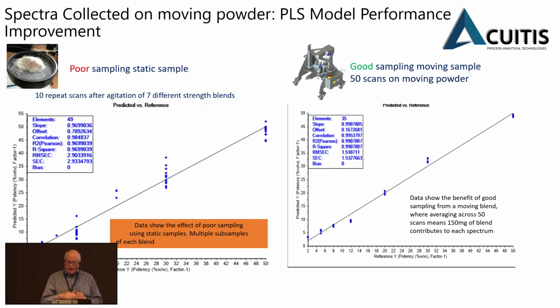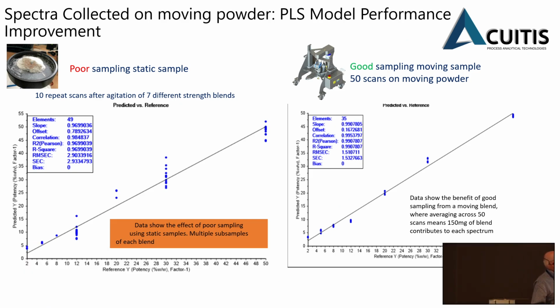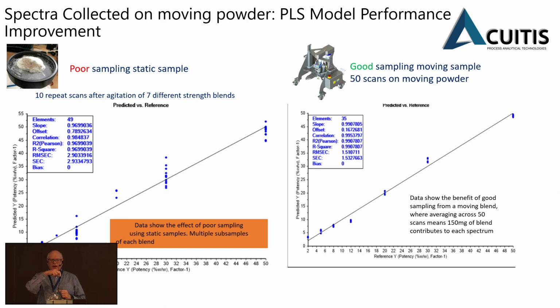Now, the way we get around that, I'll come to in a minute, but here is some evidence that this is a real big problem. Myself and Owen actually did this work. We scanned a blended powder on a dish where we were just covering the fiber optic probe. So we would put the powder there, scan it, and then move it with a stick, agitate it and scan it again. For each of these blends, there were 7 of them, we would scan them 10 times, agitating the powder between scans. But every time, the powder was stationary while it was scanned. We then tried to make a calibration using that data, and you can see how bad that is. That is all to do with the fact that you're only collecting a spectrum from 3 milligrams of powder, and it isn't representative in terms of a unit dose weight.